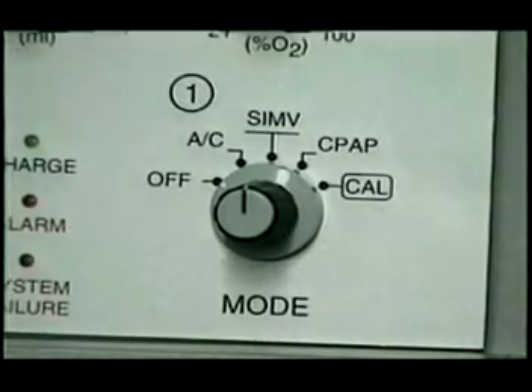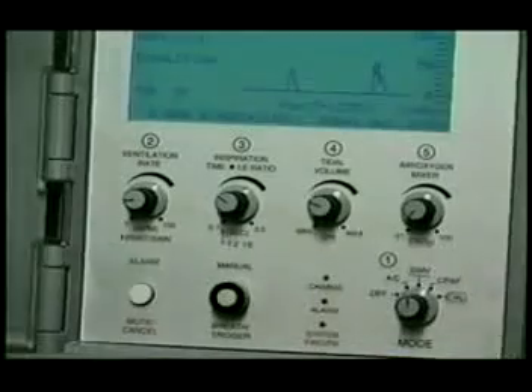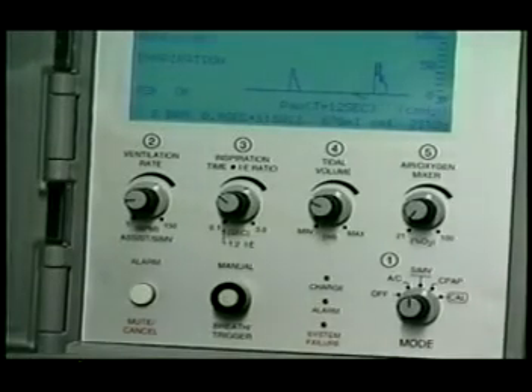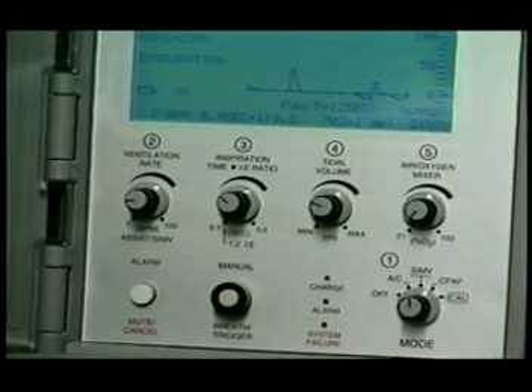In the SIMV mode, the ventilation rate is also the default rate. The patient is allowed to breathe spontaneously and assume the entire work of breathing between mandatory breaths generated at the default rate. For example, if the patient is receiving 6 mandatory ventilations per minute while spontaneously breathing at a rate of 12 breaths per minute, then 6 of the breaths will be assisted and the other 6 will be spontaneous, with the patient assuming the entire work of breathing.